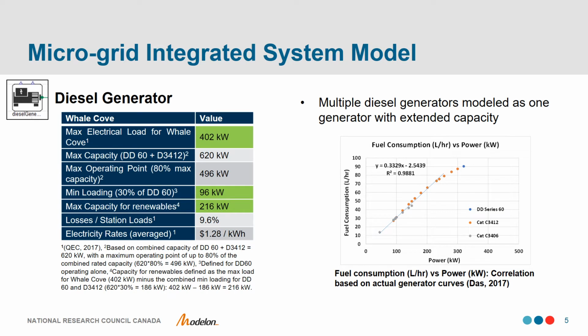In the next few slides, we will review each component model included in the microgrid application framework. The first model is the diesel generator. Although multiple generators exist at Whale Cove, for simplicity they were modeled as a single generator with a fuel consumption versus power correlation derived from the actual Whale Cove generator curve, shown on the right. The generator was constrained to operate above a minimum loading level of 96 kilowatts based on the operation of a single generator. To determine the available capacity of the microgrid for renewables, we looked at the difference between the maximum electrical load for Whale Cove of 402 kilowatts and the minimum loading level of the maximum generator capacity of 186 kilowatts, showing that there was room for 216 kilowatts of power to be provided by renewable energy sources.